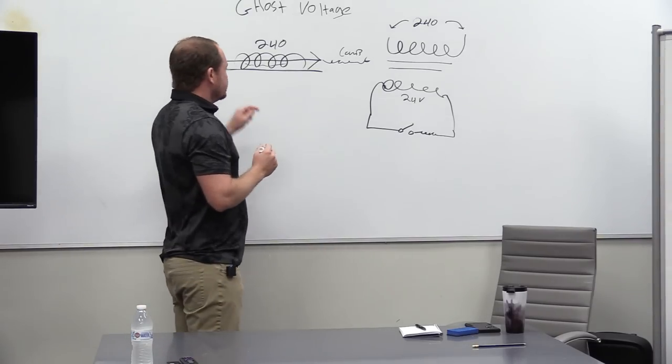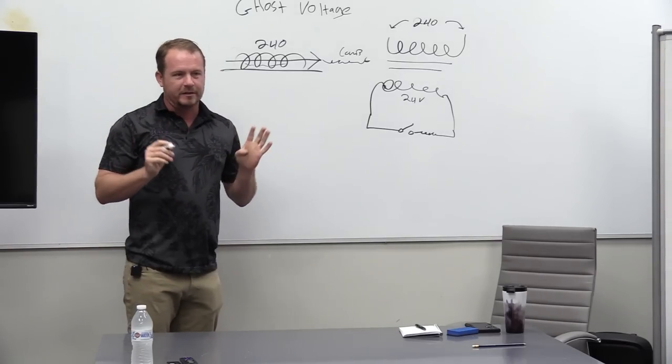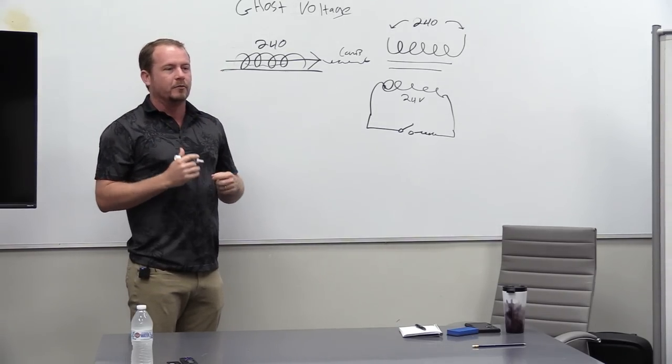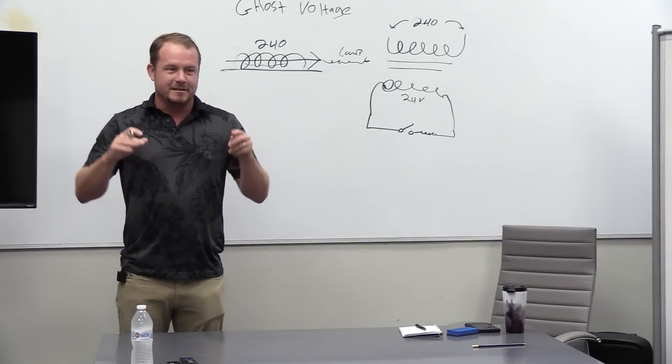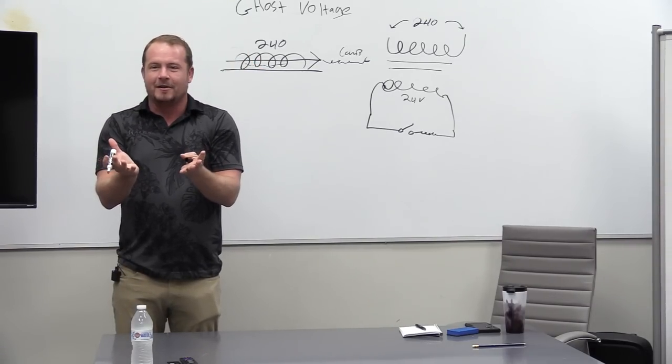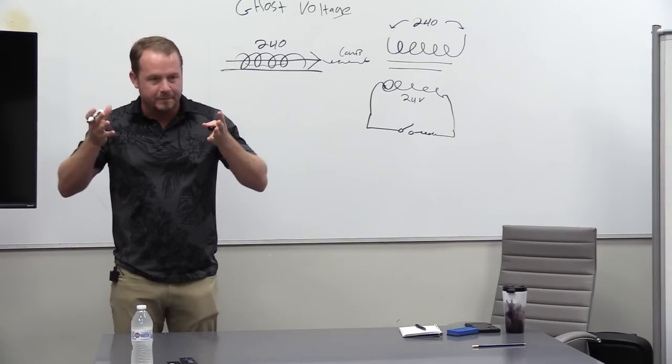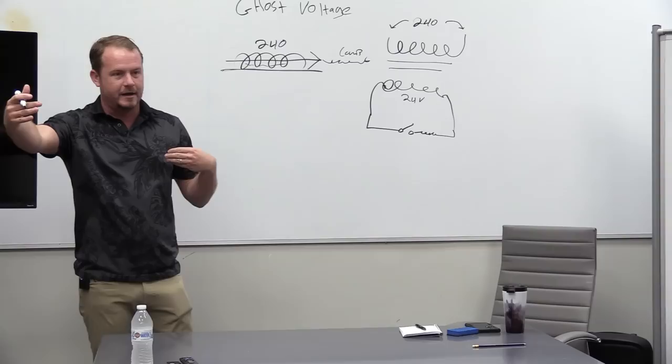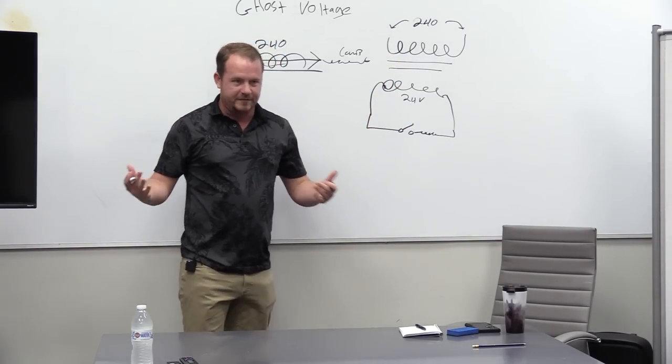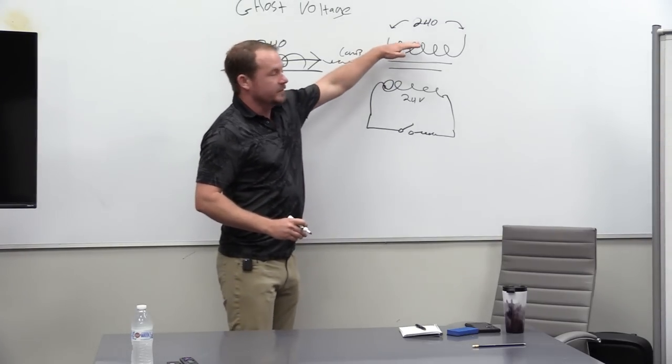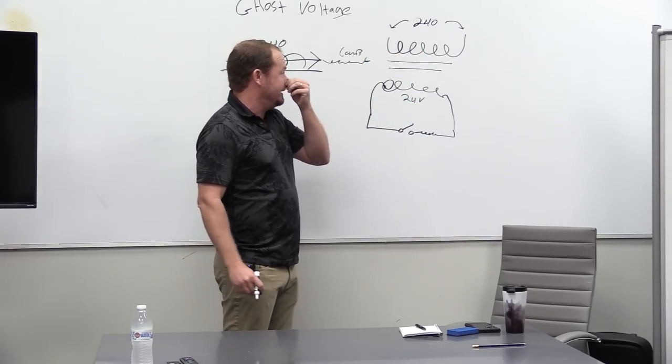Same thing that happens in a transformer, when we go from the primary and we induce a current in the secondary, we can do the same thing by running two wires next to each other. This is why you don't take low voltage wires and run them right next to high voltage wires. This is why, especially with more complicated control systems, you have to be really careful about that. And you have to be careful about grounding and all that stuff, because you'll get these induced voltages that mess with the controls.